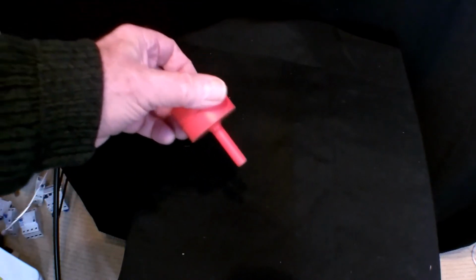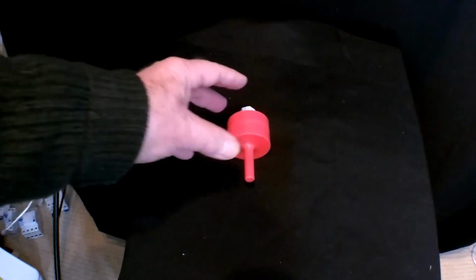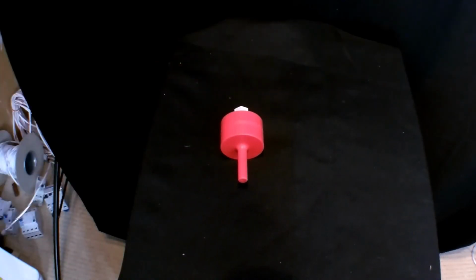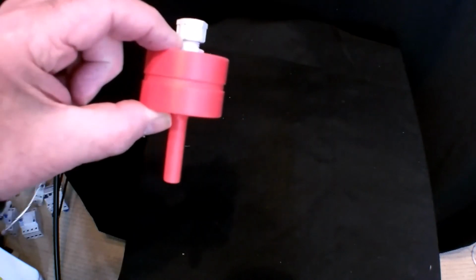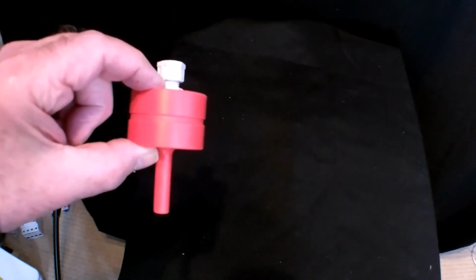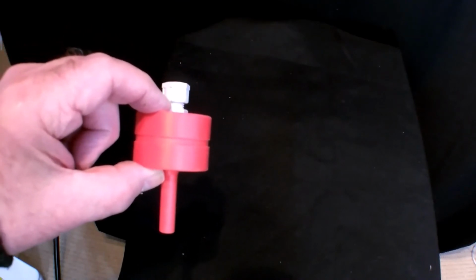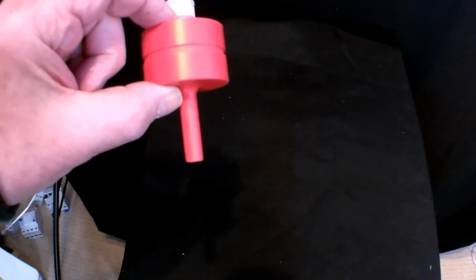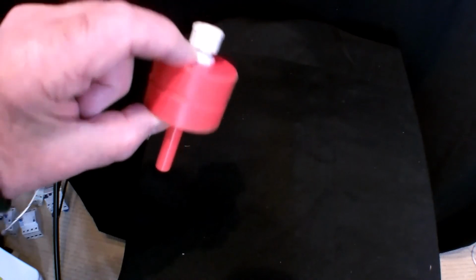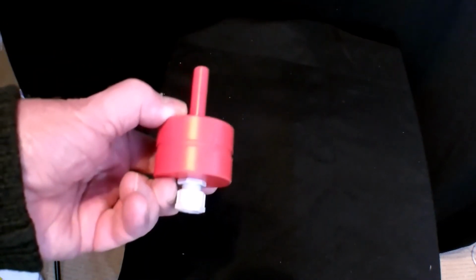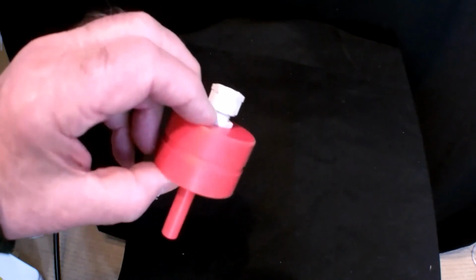Very often if you put the sensor in a heat exchanger, it will be reading slightly high at times, and if you shut the system down and you're using it as a high limit probe, it can shut the system off and can interrupt backwashing. So we always recommend using this prior to the heater, just a few inches before it, so that it doesn't get caught up with any excess temperature problems when you switch off or in the middle of a backwash.